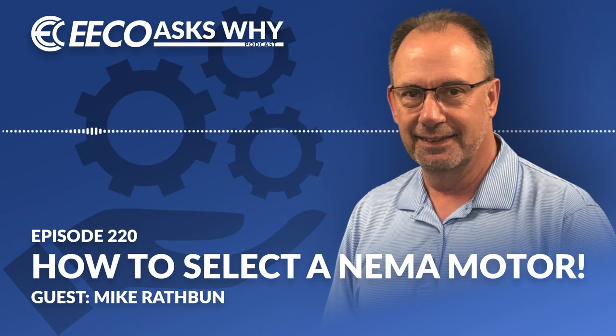I think one thing I'd add that we hadn't touched on at this point is taking into account if an application is using a VFD as opposed to an across the line starter. Starting with a motor that's vector rated or vector duty rated builds in reliability that applies directly to some of the bad characteristics that a VFD brings into a motor life cycle, and builds those characteristics into the motor from day one. Not to say that you can't operate a conventional AC induction motor on a VFD, but if the application is critical and you're not crazy about changing out motors in the middle of the night, ensuring that motor is a vector rated duty motor probably would pay off in the long run.